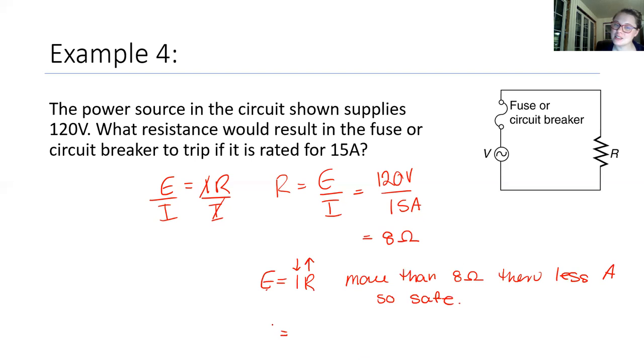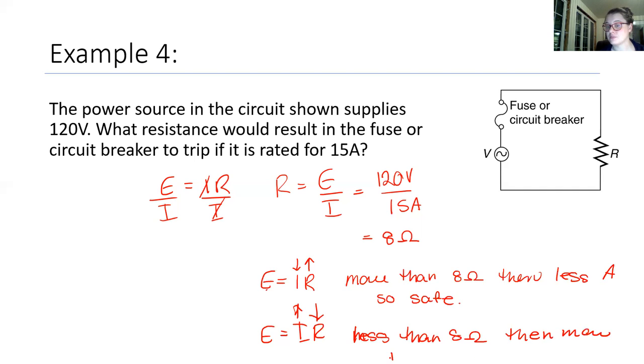But if we decrease the resistance, so there's less resistance, the current would increase to more than 15 amps. If we have less than 8 ohms, then we're going to have more than 15 amps. So this is the scenario: we would have to have less than 8 ohms for the breaker to trip.